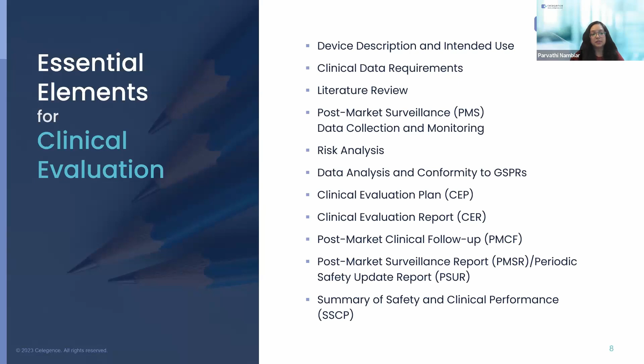So how to develop a comprehensive clinical evaluation strategy? As I mentioned previously, there is some critical information that needs to go into the CER, such as relevant scientific information on the safety, performance, the design, and the intended purpose of the device, along with all the available clinical investigations that have been carried out on the subject device, either internally by the manufacturer or data that we've gotten from other clinical investigation databases. And we also need to present information that's available on the alternative treatment options or alternative therapies that are available on the market, along with all the PMS data that's been generated for the subject device.